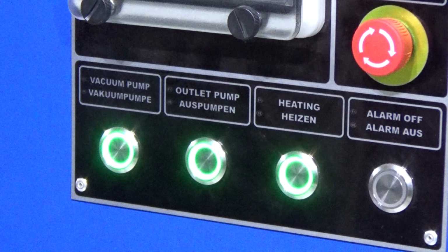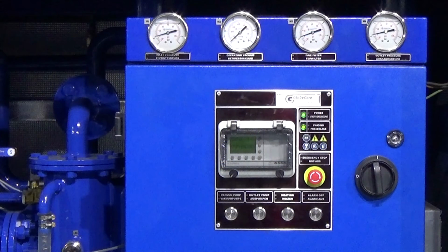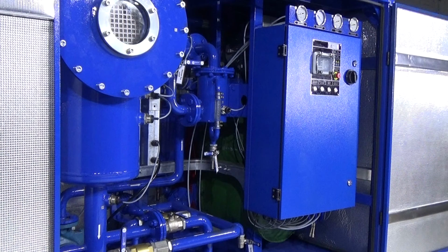When the oil temperature is less than 50 degrees Celsius, bubbles may be observed in the vacuum chamber sight tube. 7. Control the vacuum in the system as indicated by the operation vacuum gauge. If the oil is highly contaminated, vacuum may cause foaming of the oil. In this case, air will enter the unit through the air inlet electromagnetic valve, reducing vacuum in the system. In this case, process the oil in several cycles.